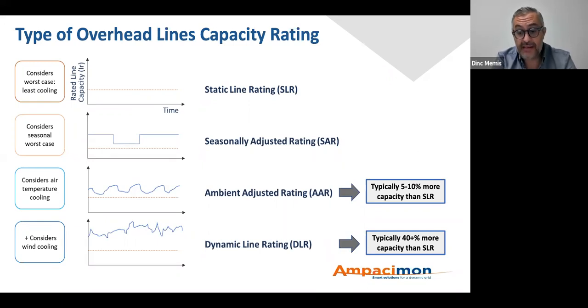And the last one is the direct measurement method, which is sensor-based dynamic line rating. It uses devices, or sensors as we call them, directly coupled to the line, measuring conductor temperature, tension, sag and clearance, from which the line's thermal rating is determined in real time. It is proven to provide more than 40% capacity compared to static line rating. You also see that it considers wind cooling, which I will refer to a little more on my last slide.